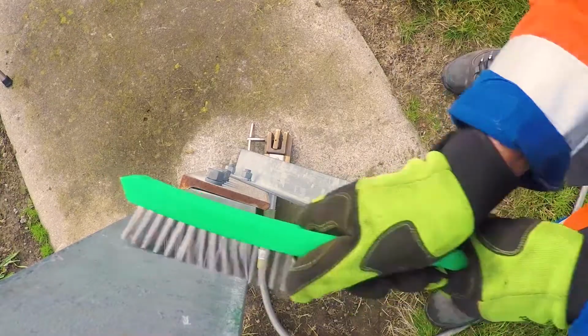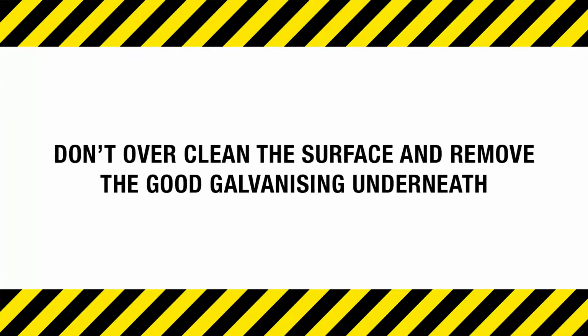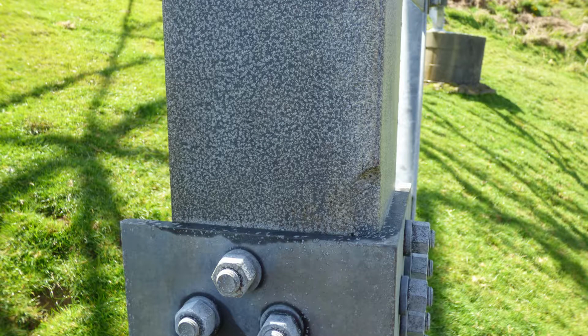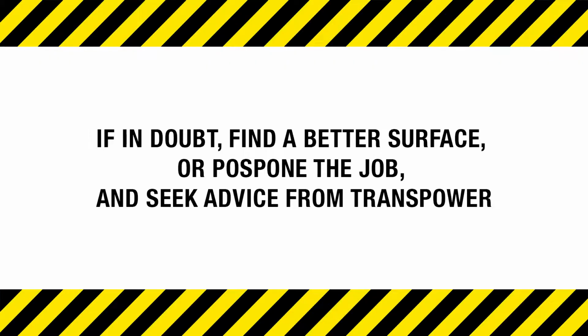Make sure that when you clean a galvanized steel surface, you don't over-clean the surface and remove the good galvanizing underneath. Zinc is an excellent conductor, so don't remove it. There may be situations where a galvanized surface is so badly corroded that using it as a tail clamp attachment point would be hazardous. If in doubt, find a better surface or postpone the job and seek advice from Transpower.